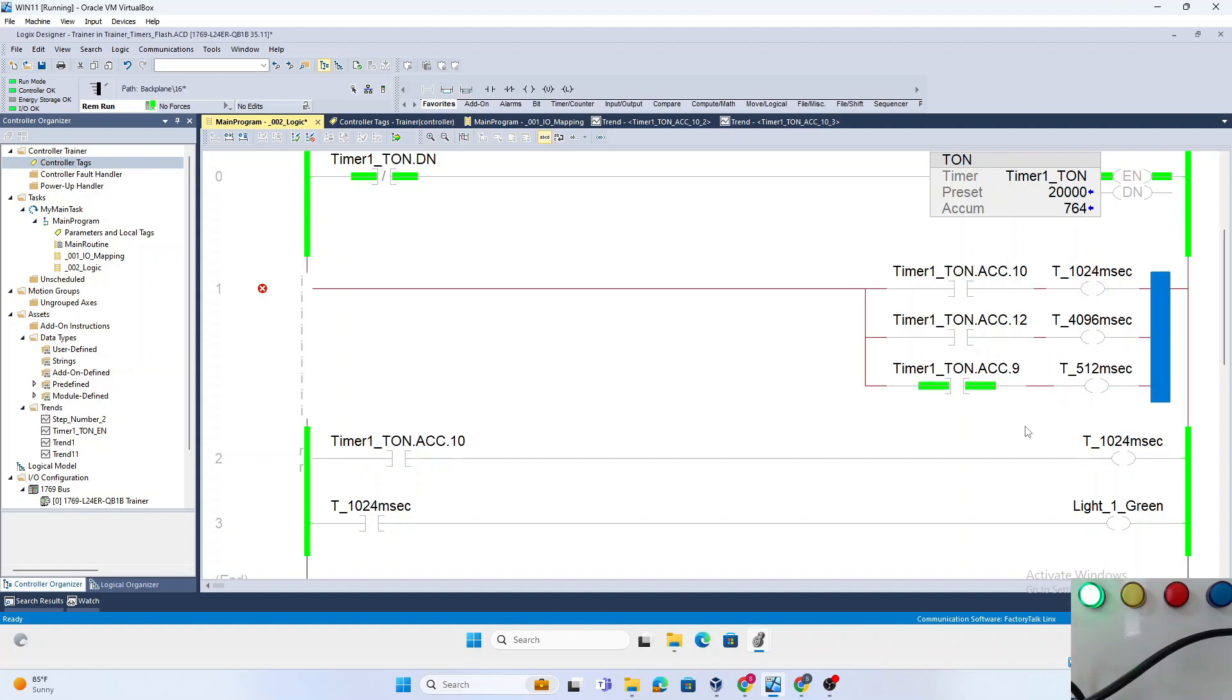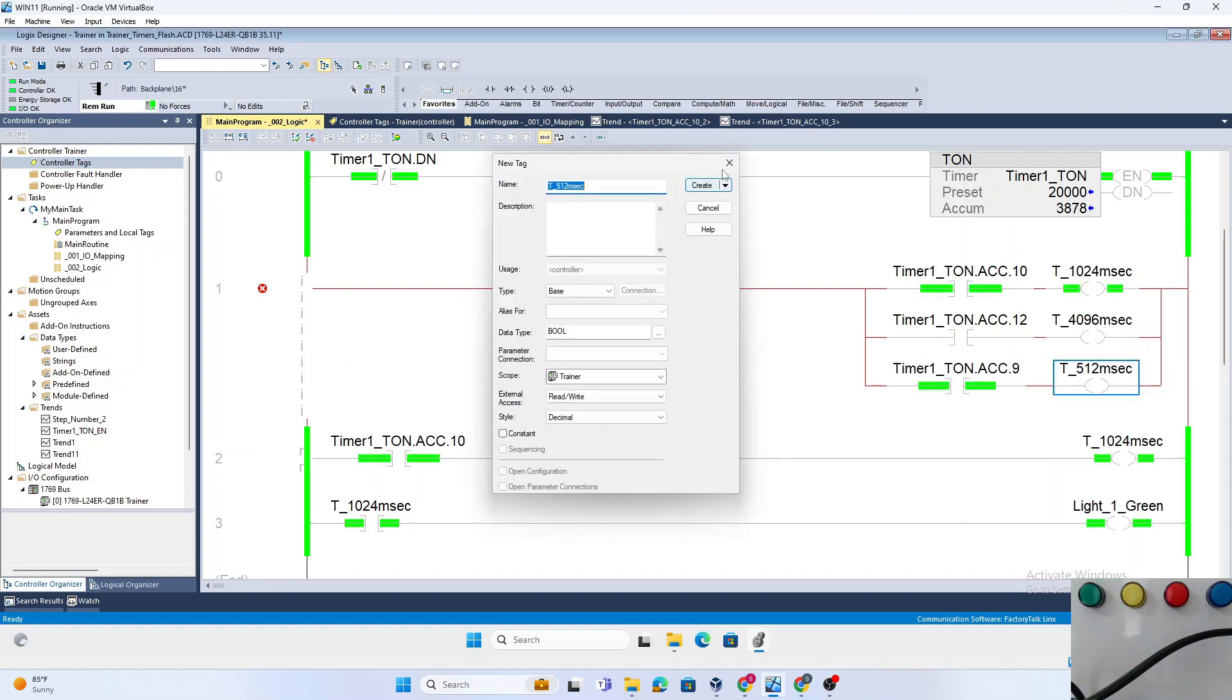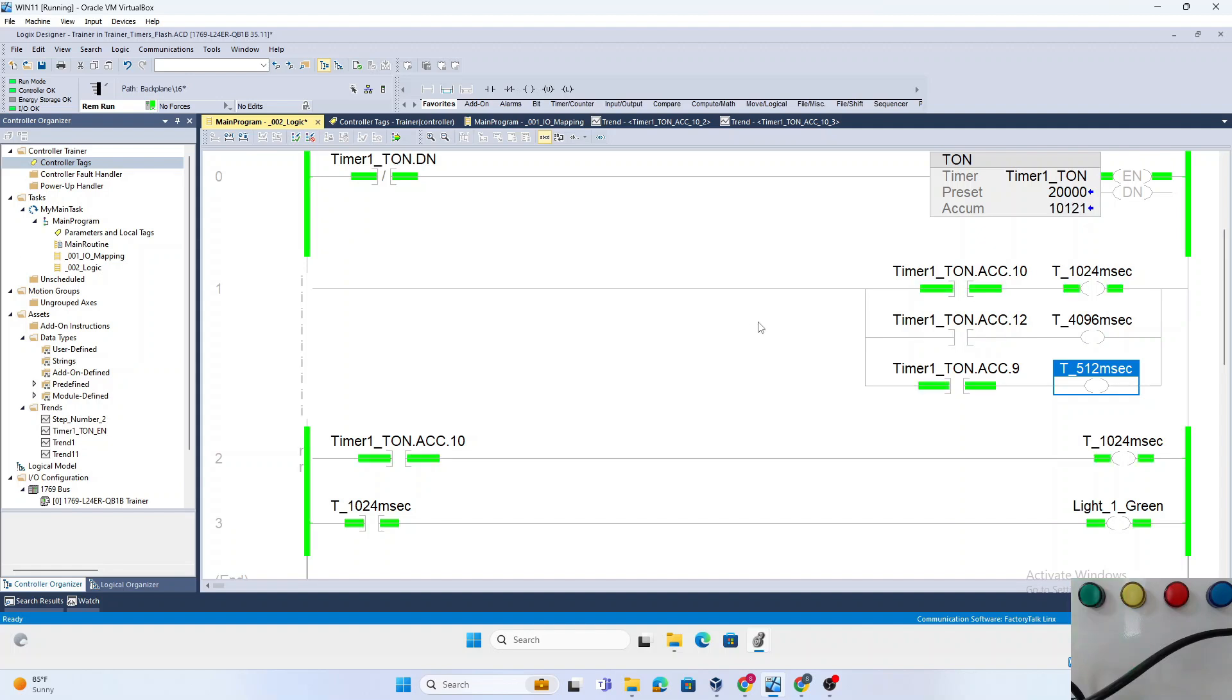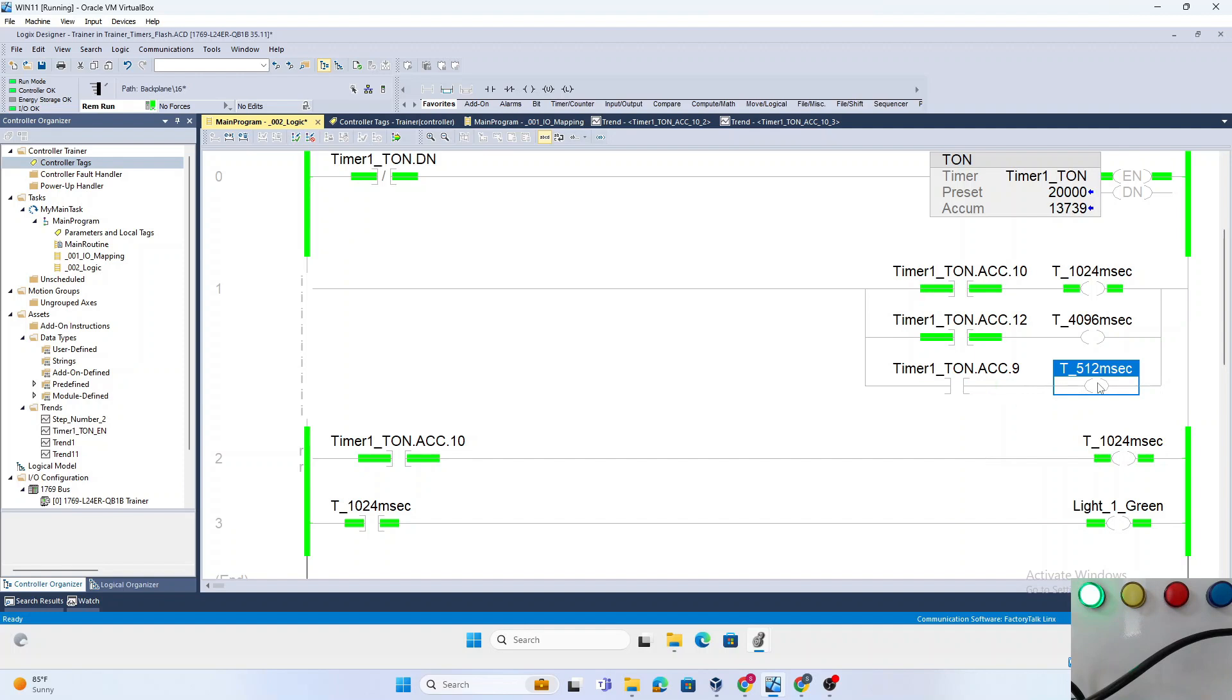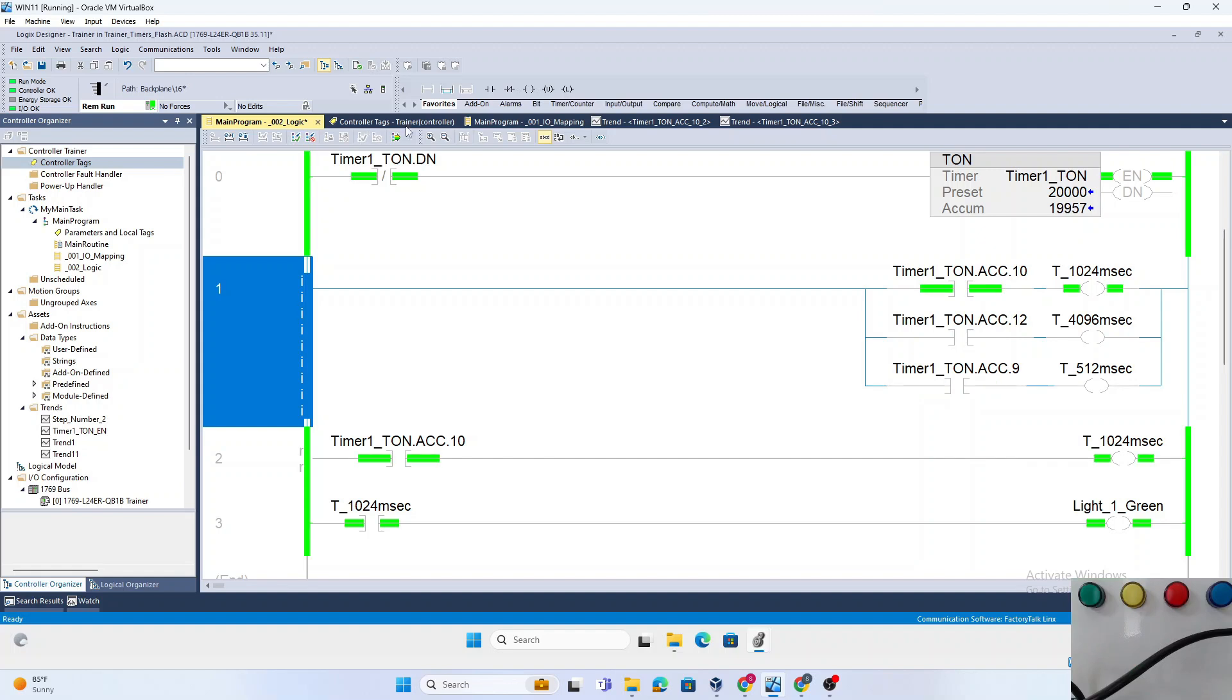We can also build a 512 millisecond flasher by using the dot 9 bit. Depending on your application, you could map all of these before or as you need them. I use bits 9, 10, and 12 to give me a half-second flasher, one-second flasher, and a five-second flasher signal.